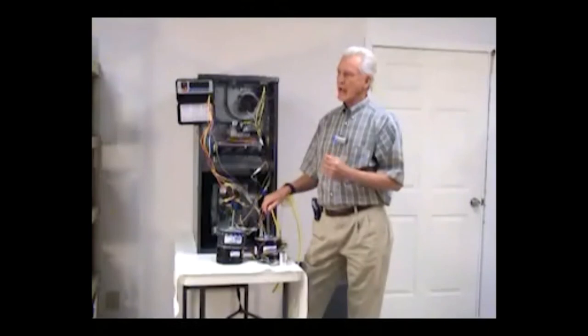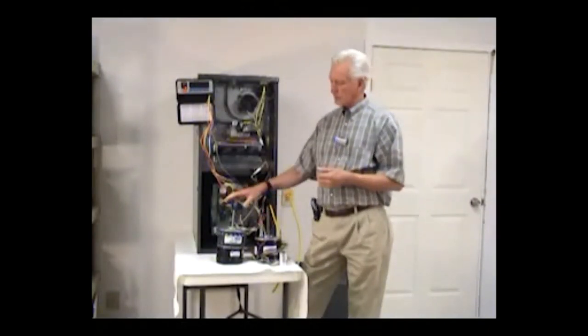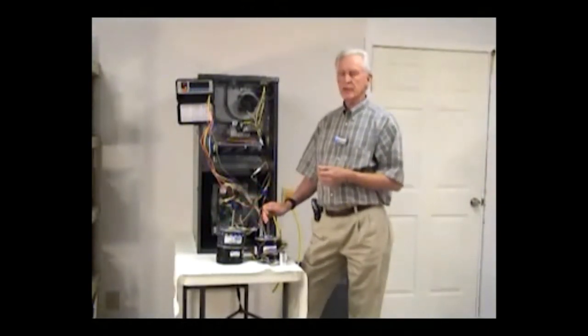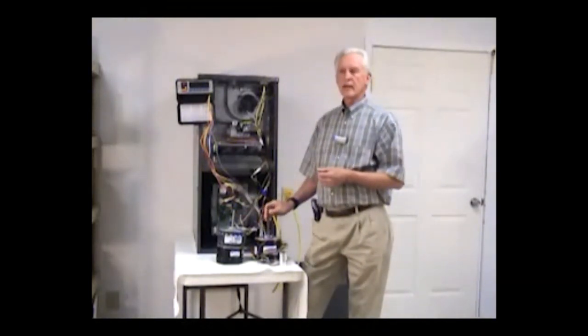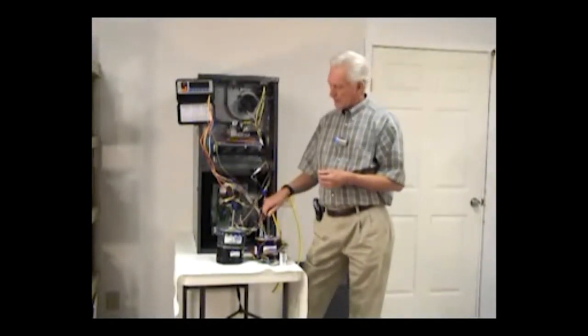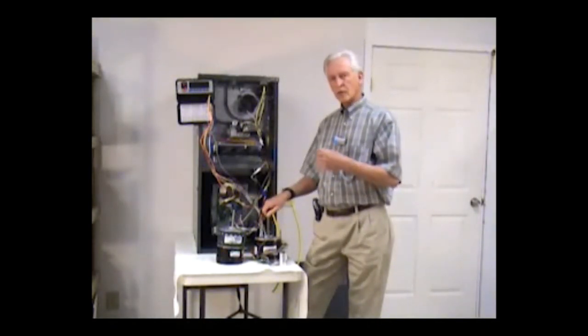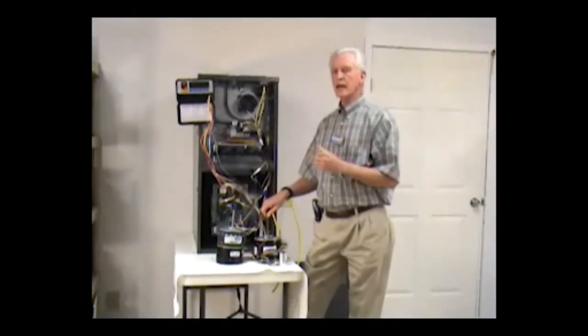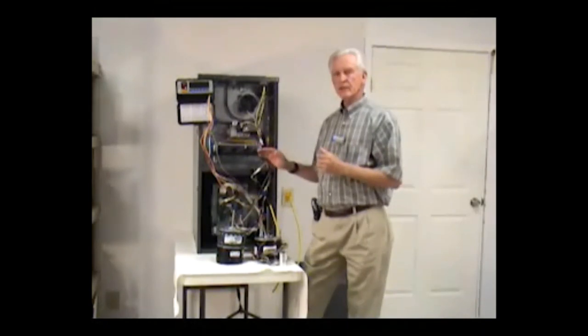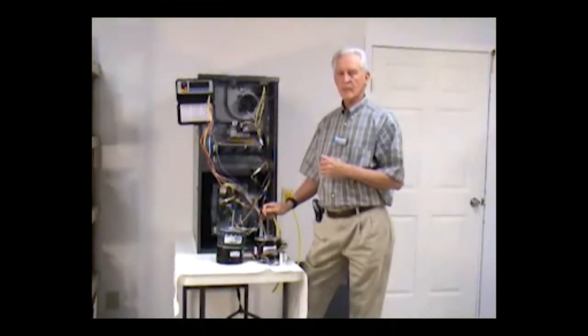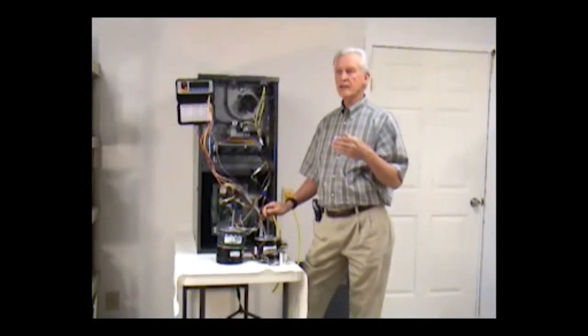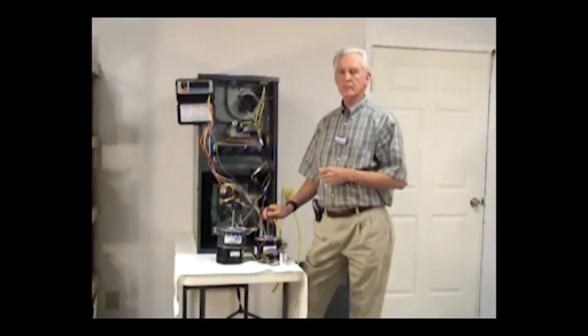What happens to the amperage draw, and that's where we're going when we make a comparison to the ECM motor, is the PSC motor, split capacitor motor, that amperage draw will take a slight dive. It will go down slightly as we increase the external static pressure. It isn't going to be dramatic, but it will drop off. What does happen, though, that is dramatic, is the CFM also begins to deteriorate at that stage of the game.